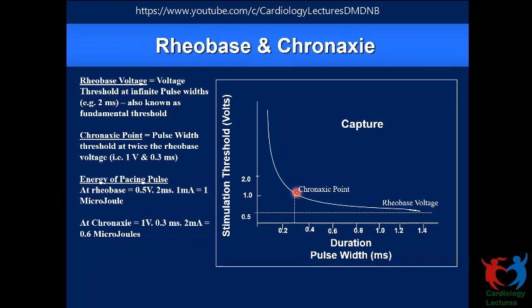So if you want to scientifically test when a patient comes for a follow-up, that is what we have to do, but that's not possible because your department is too busy, so you cannot do that on every patient. But in a well-implanted system, the chronaxie pulse width usually is between 0.25 to about 0.5 millisecond, and that's why most pacing systems have a nominal pulse width of 0.4 to 0.5 millisecond. And in fact, the current generation Micra pacemakers have a nominal pulse duration of 0.24 millisecond.